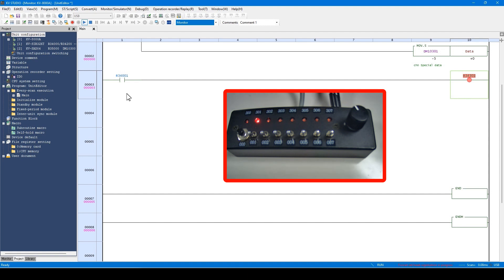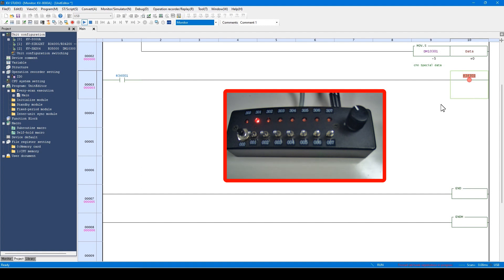Forced set is used to forcibly turn on the coil even when the execution condition is not on. On the contrary, forced reset is used to forcibly turn off the coil even when the execution condition is on.